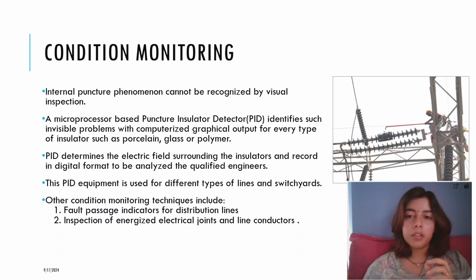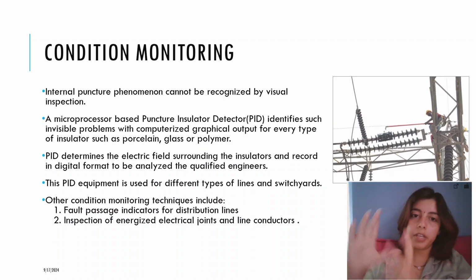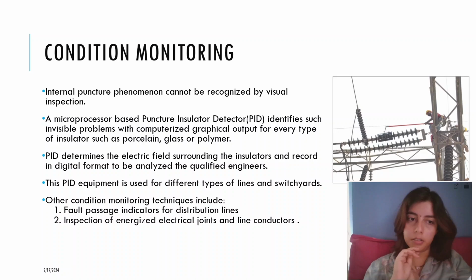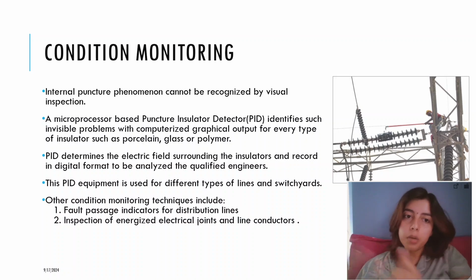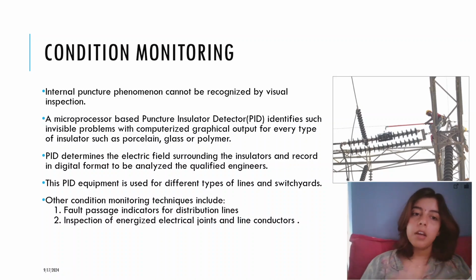In insulators, there can be punctures - not that there will always be, but there can be. Internal puncture phenomena cannot be recognized by visual inspection of the equipment. We cannot see if there may be internal puncture or cracks in the insulators. We need to know whether there is a puncture so we can replace the insulator with a better working one. For this, we use a special microprocessor-based device called a puncture insulator detector.